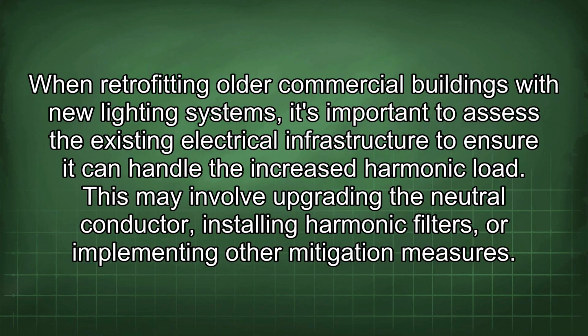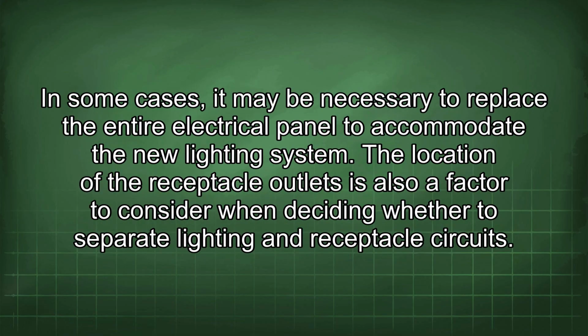When retrofitting older commercial buildings with new lighting systems, it's important to assess the existing electrical infrastructure to ensure it can handle the increased harmonic load. This may involve upgrading the neutral conductor, installing harmonic filters, or implementing other mitigation measures. In some cases, it may be necessary to replace the entire electrical panel to accommodate the new lighting system.